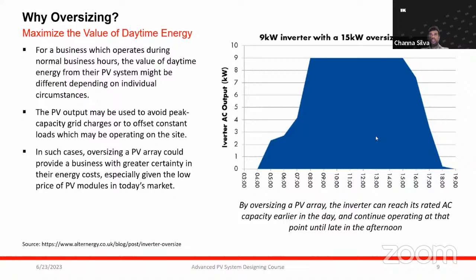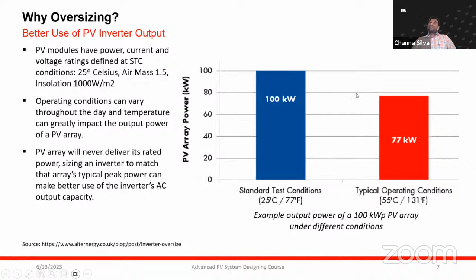What are the other benefits? If you don't look at just the rated power — say you size with a 100 kilowatt inverter — in this other case you could size with a 77 or 75 or 80 kilowatt inverter. So you can save some budget from the inverter itself at the beginning, reducing the overall inverter budget.